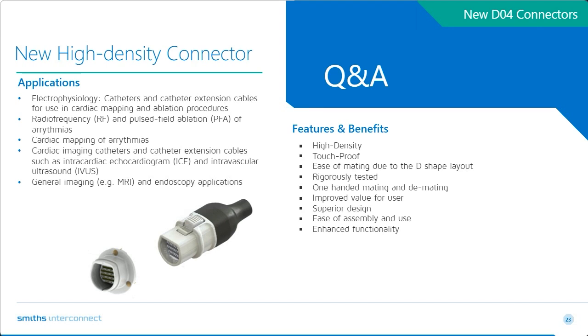The trade-off is you need a fairly high voltage to create a lesion in the heart. We're seeing north of 1.8 kV as a starting point, going up to around 3 kV for some systems being sampled. Right now we've designed one at 2 kV for a current system we're working on, but if higher voltages are required, we do have means to raise our voltage withstand even higher.